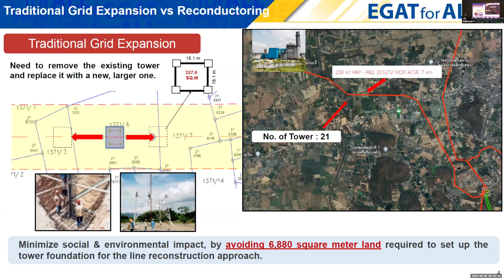This slide shows the process and timeline of traditional grid expansion, the blue one, and reconductoring, the yellow one. If we choose the blue way by building a completely new line, we must compensate the community for the right of way once again, because it's necessary to remove the existing tower and install a new one, as I showed on the previous slide. This procedure is managed by the Energy Regulatory Commission of Thailand, or ERC. It takes a long time and depends on the community area. Furthermore, the construction process of building a new transmission line takes longer than reconductoring. Finally, please consider the power plant scheduled commercial date, or SCD, of June 2033. Reconductoring is the only possible way.